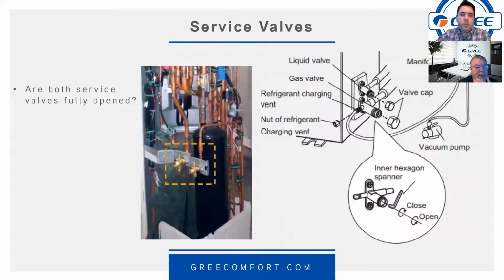Let's see. And then move to the service valves. Surprisingly enough, this does happen, but are both service valves fully opened? And there are two on there. Sometimes someone will neglect to open one of them, and that's going to cause a high pressure situation that can give you that E1. That's really easy to do on a multi-zone system where you've got 2 valves per indoor unit. So you got a bunch of valves that you have to make sure are opened all the way. Right. Yeah, real good point.